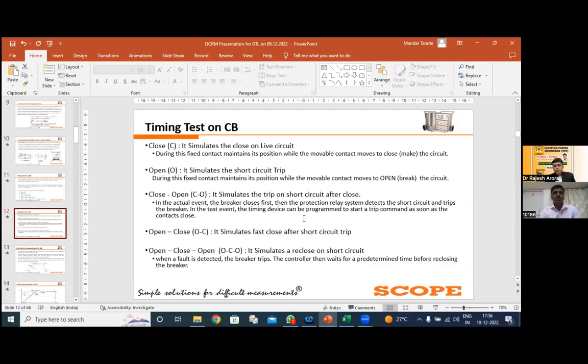Simply in case of the close, we are simulating the close on the live circuit, or in case of trip, we are simulating the short circuit trip. Here, the important thing is that in the CO, the delay TCO plays a significant role, because our expectation is that it simulates the trip on the short circuit after close. So to perform the immediate tripping, our expectation is that once the auxiliary changeover happens, our trip command should be available right there. It should not wait further. So the thumb rule is that your delay TCO at the time of performing the CO operation must be close timing minus 10 milliseconds. This is very important and plays a very significant role at the time of performing the CO operation.